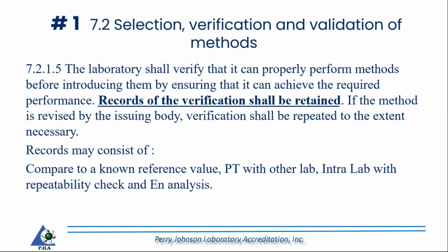Verification. Before introducing a method, the laboratory shall verify that it can properly perform the method by ensuring it can achieve the required performance, and records need to be maintained. With accreditation scope expansions, say you're doing calibration in various areas and you want to expand your scope and you put in a scope expansion for PJLA, it's going to be assessed. We want to see records that you're not just adding it, that you actually verified that you can achieve the intended results.